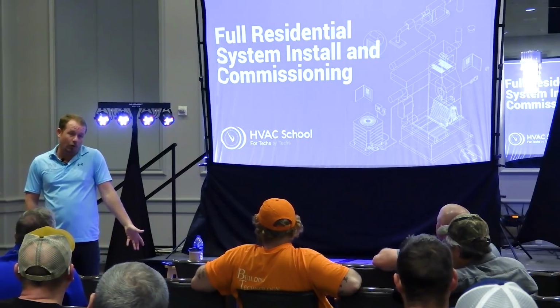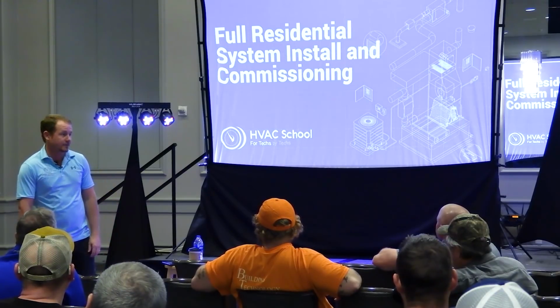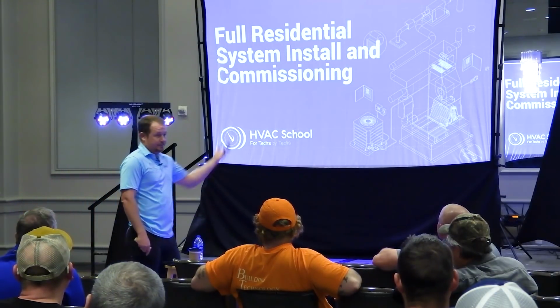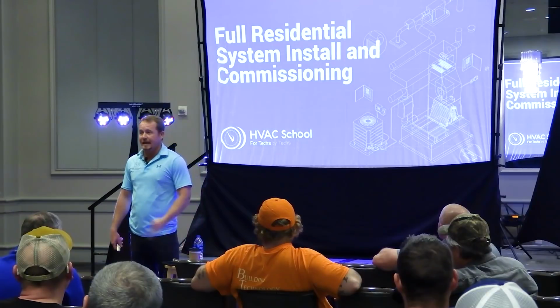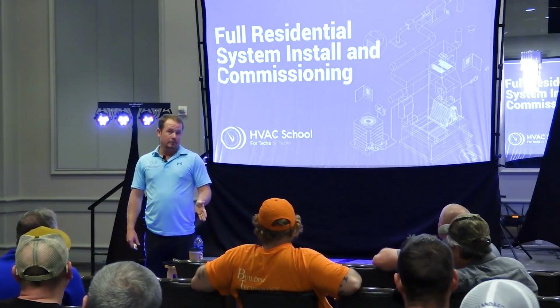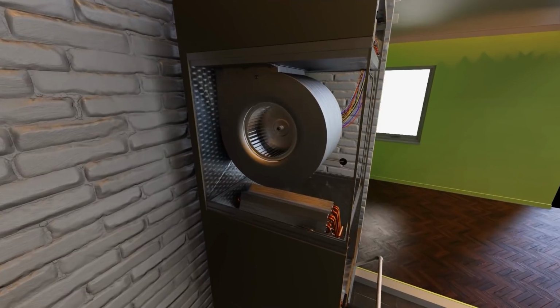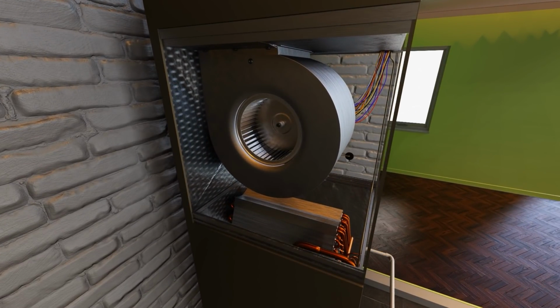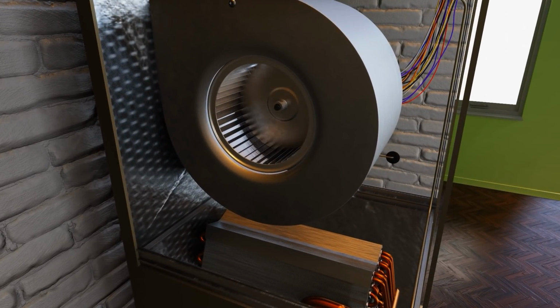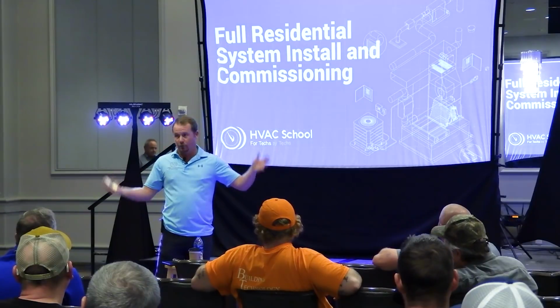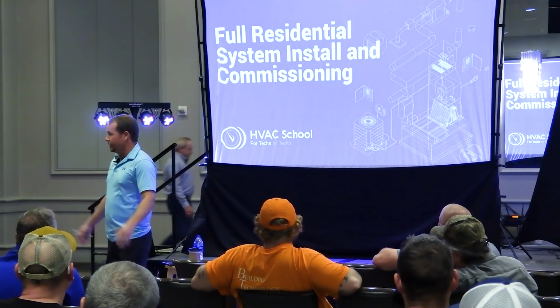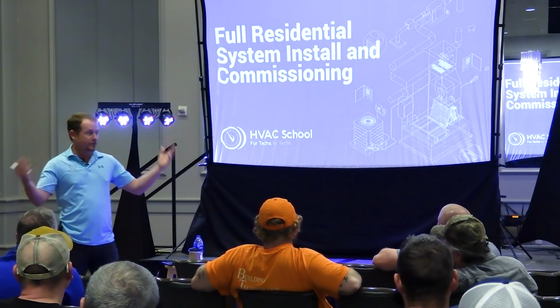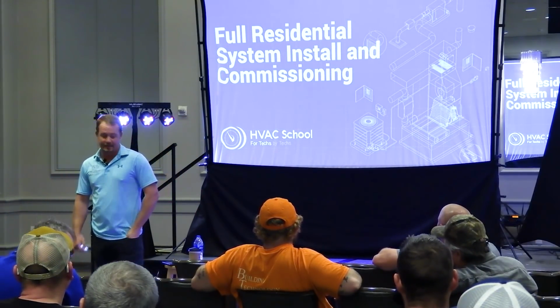You could use that, or you could just be good at catching all the problems that could cause the system not to be producing the airflow that it's supposed to produce. Because static pressure alone is reliant on the airflow output of the blower. And if something is wired wrong, or if the blower motor is programmed wrong, or if somebody put in an aftermarket motor, or put in a different size blower wheel, or the blower wheel's dirty, or who else knows what's going on with it, that's not going to be correct.